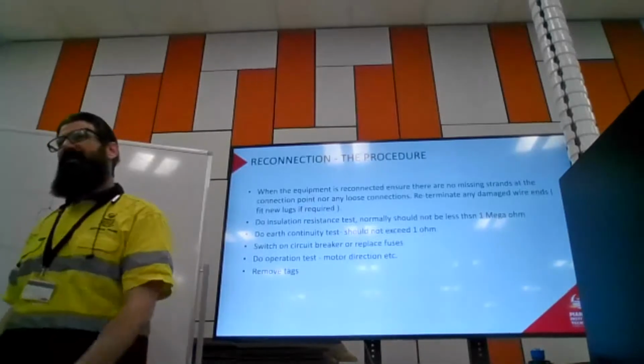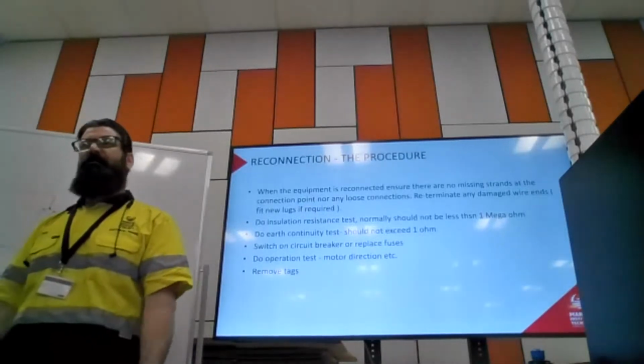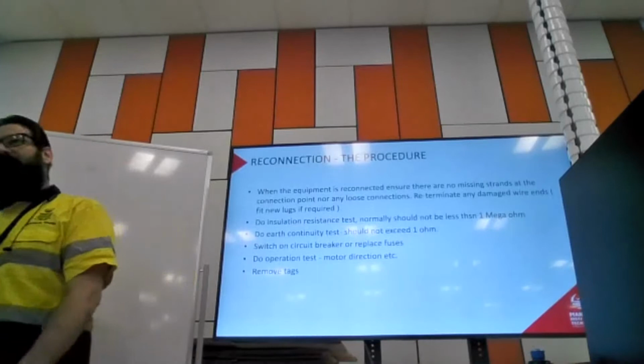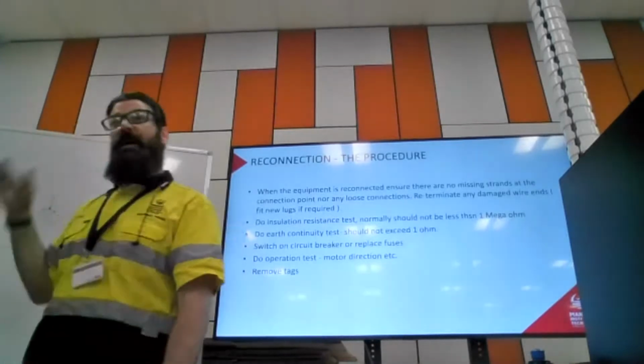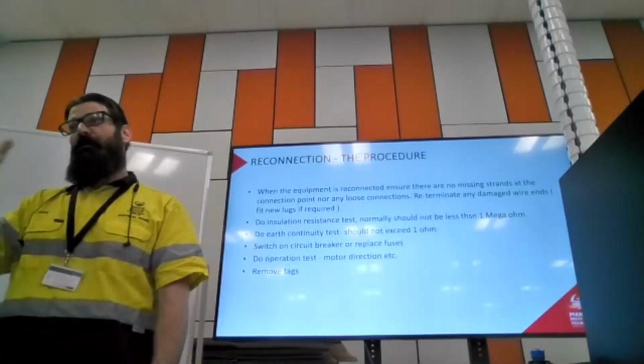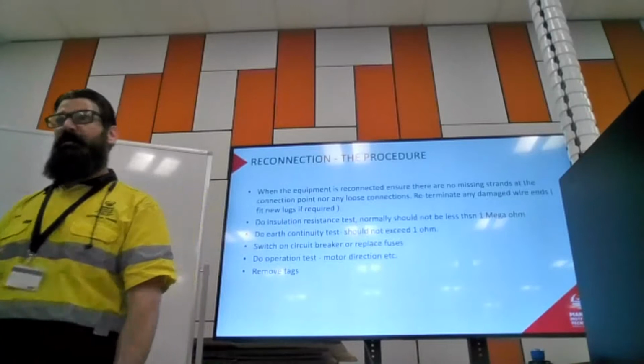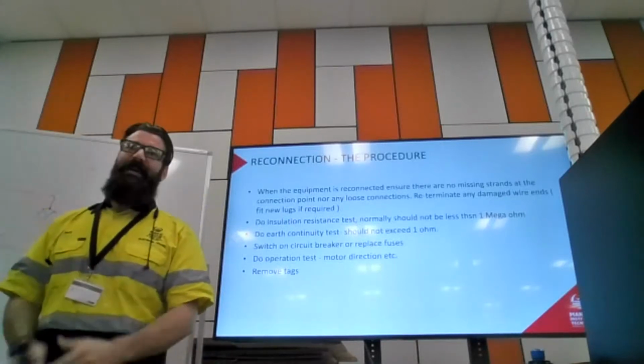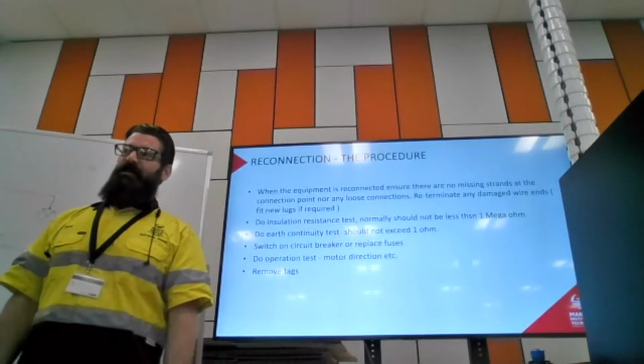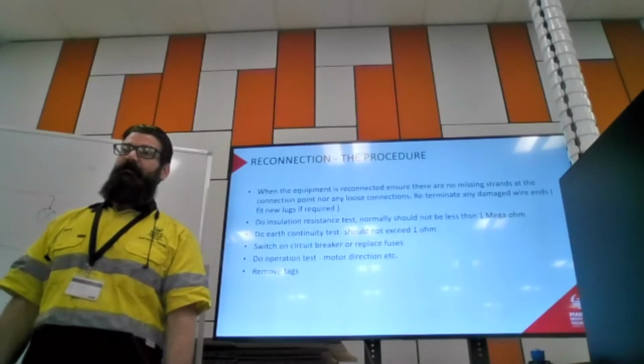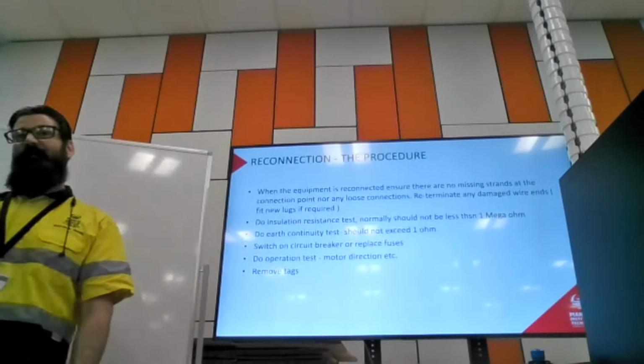It's kind of dumb, really, when I explain it all like that. It's like, well, why isn't everything 10,000 ohms? It's either safe or it's not safe, right? Like I said, the most dangerous thing that could happen in your house, if you had an earth fault, the most dangerous place you could do that is to your water system, because then it's going to zap you everywhere. There's no escaping that. But we're going to say, oh, 10,000 ohms is safe in the hot water system. It's not safe everywhere else, but it's safe there. It's either safe or it isn't.